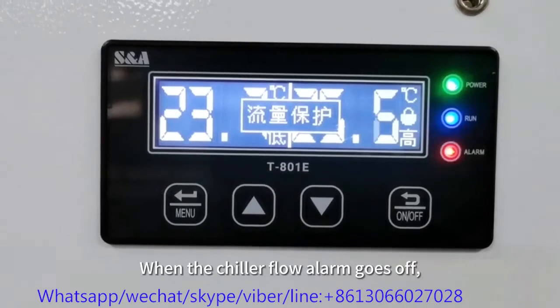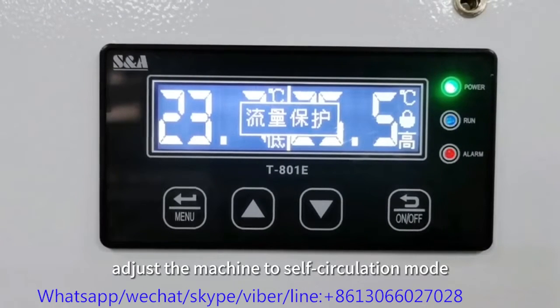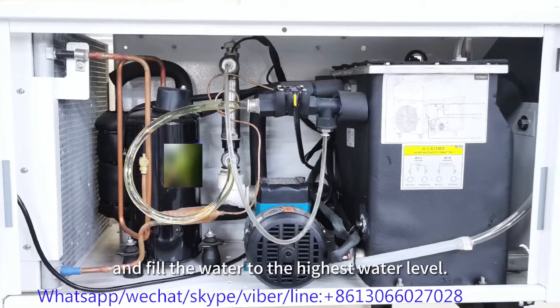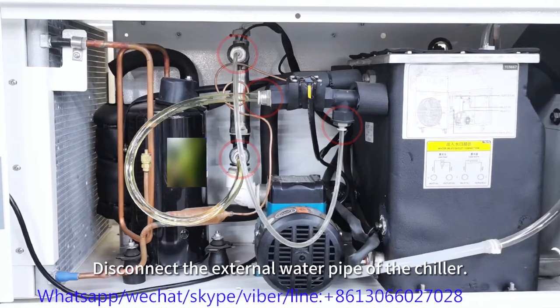When the chiller flow alarm goes off, adjust the machine to self-circulation mode and fill the water to the highest level. Disconnect the external water pipe of the chiller.